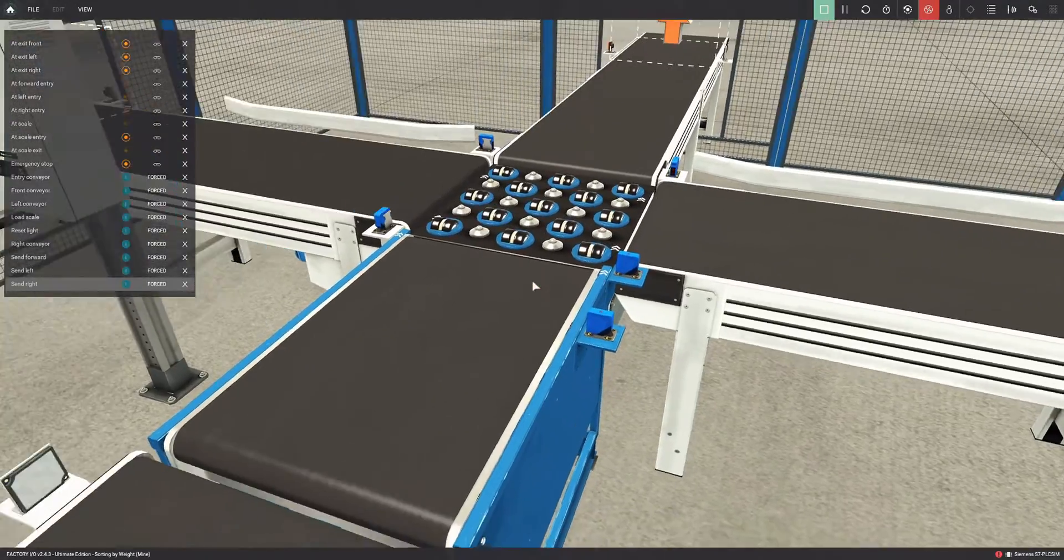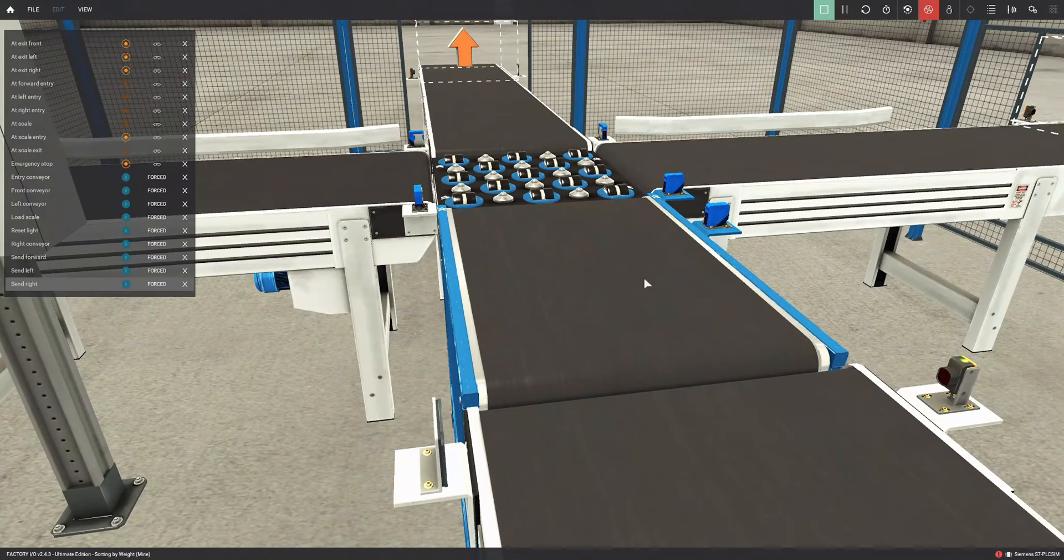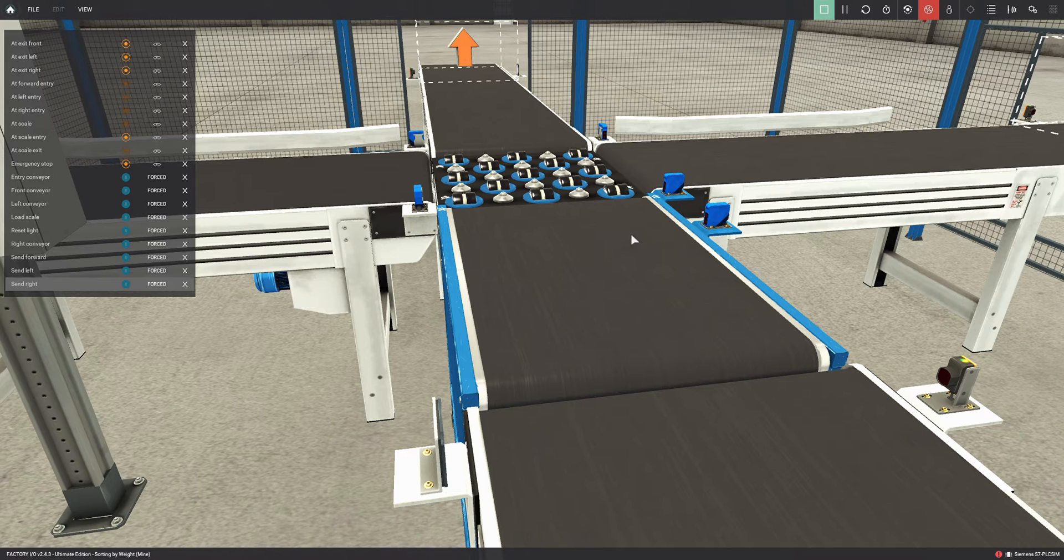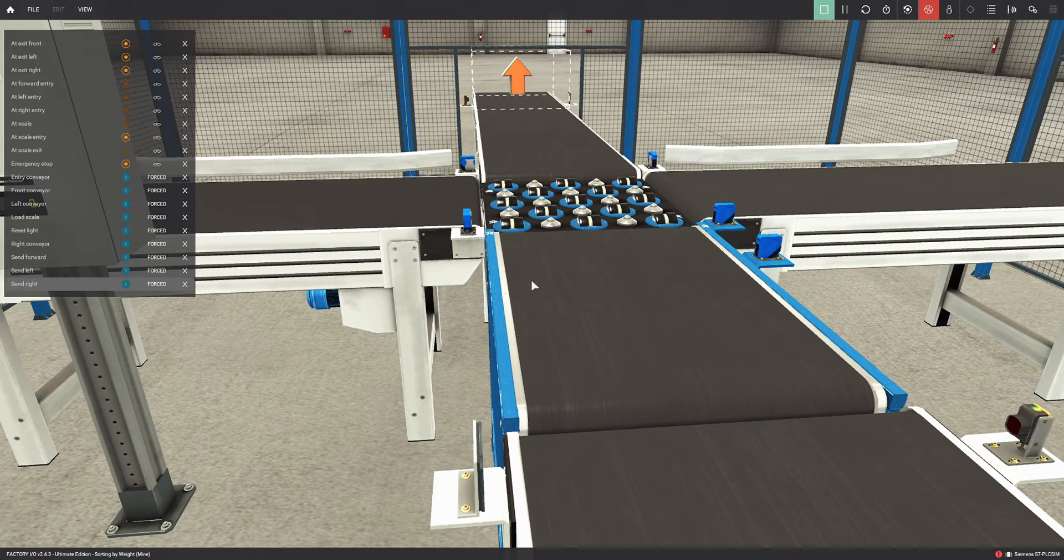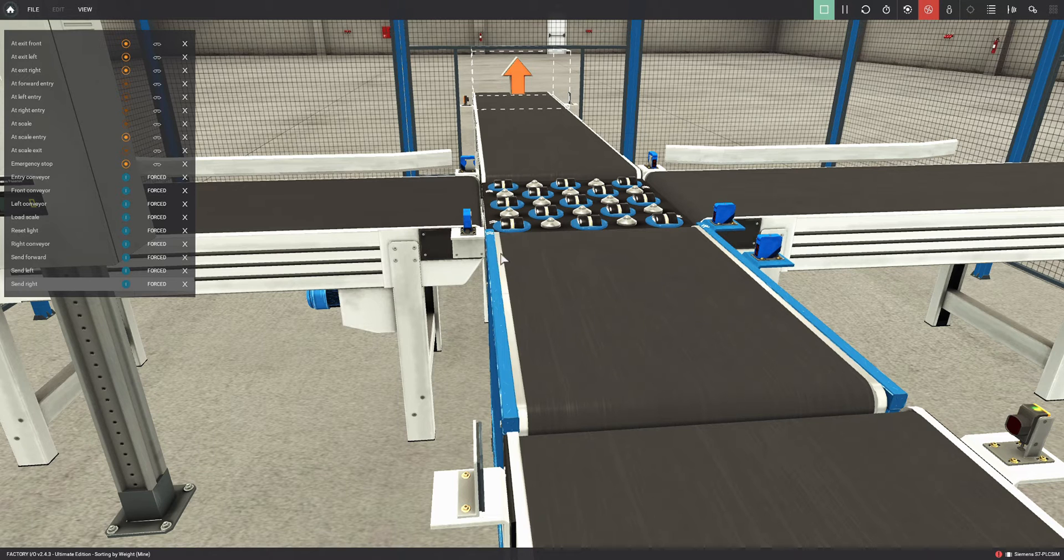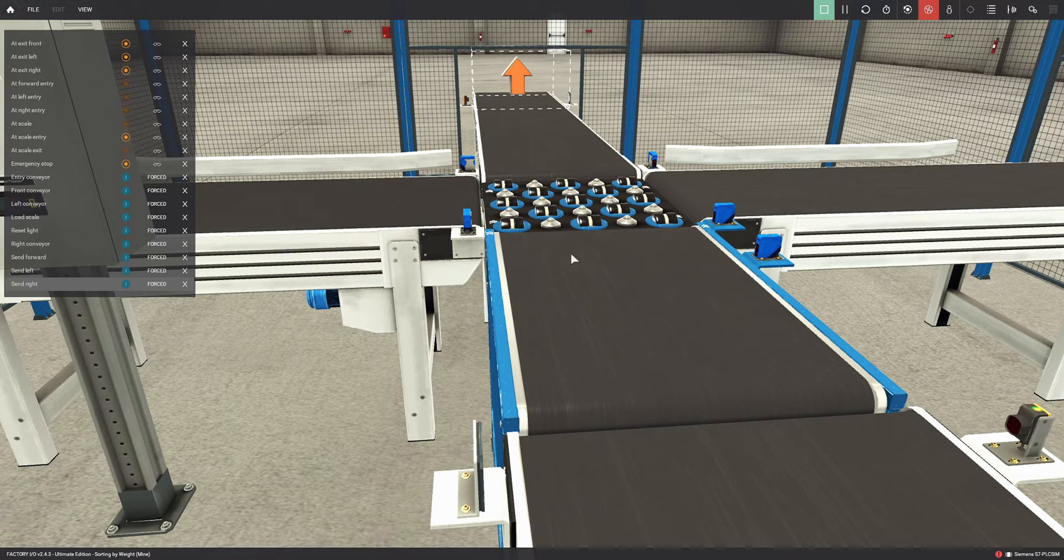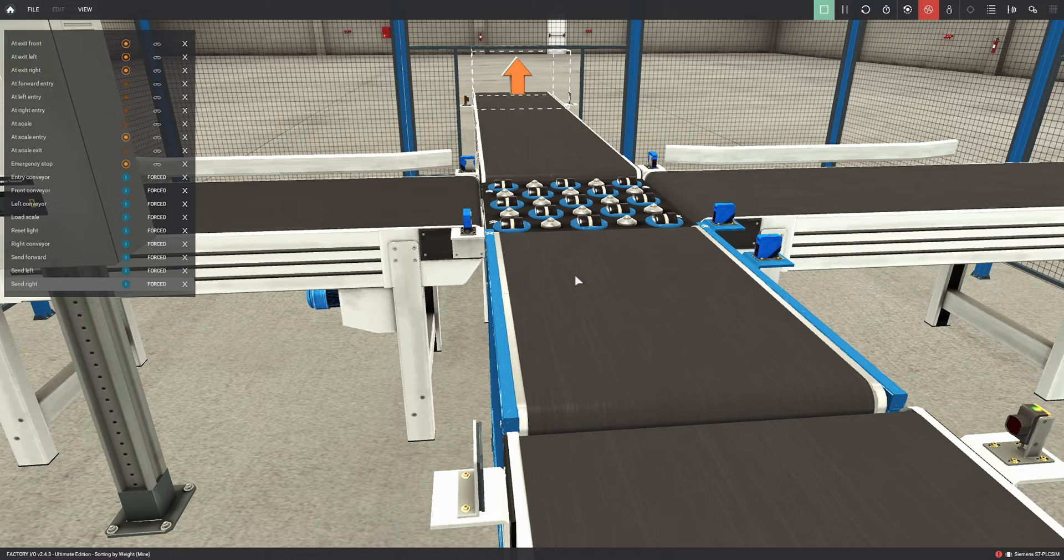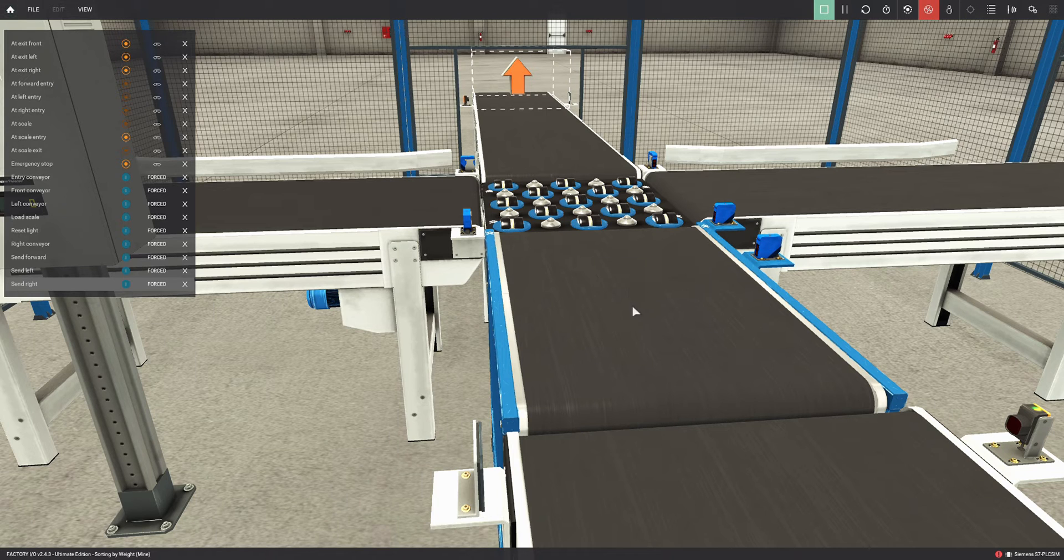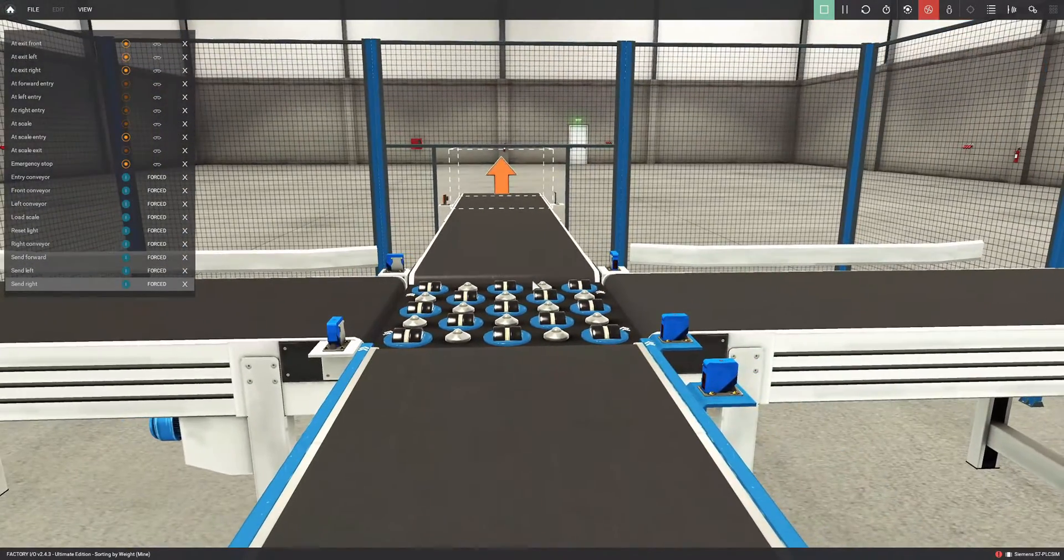I don't think there's anything else to comment. The process itself is very simple - the piece arrives here, once it's here it stops so we can weigh it precisely. Because as I said, if we weigh it while moving, the values will oscillate. If we've established ranges for pieces to go one way or another, a piece at the limit that we've set - if we've set that pieces up to 3 kilos go left, and there's a piece weighing 2.5 kilos, if the piece is moving on this conveyor, that value might oscillate and pass slightly over 3, and then this conveyor might start. So for greater precision it's better to weigh everything with the conveyor stopped, ensuring it functions correctly.